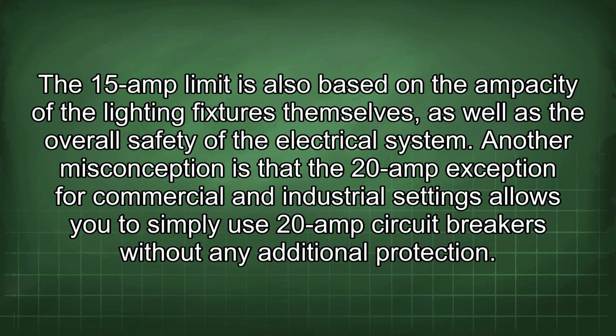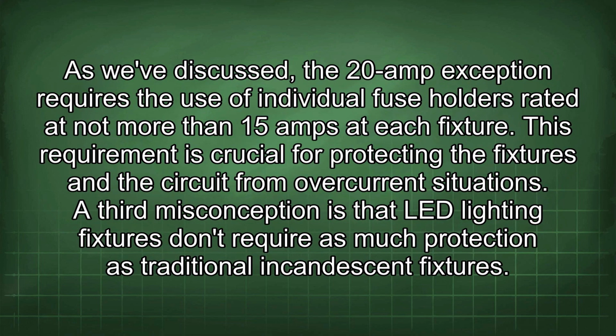Another misconception is that the 20 amp exception for commercial and industrial settings allows you to simply use 20 amp circuit breakers without any additional protection. As we've discussed, the 20 amp exception requires the use of individual fuse holders rated at not more than 15 amps at each fixture. This requirement is crucial for protecting the fixtures and the circuit from overcurrent situations.